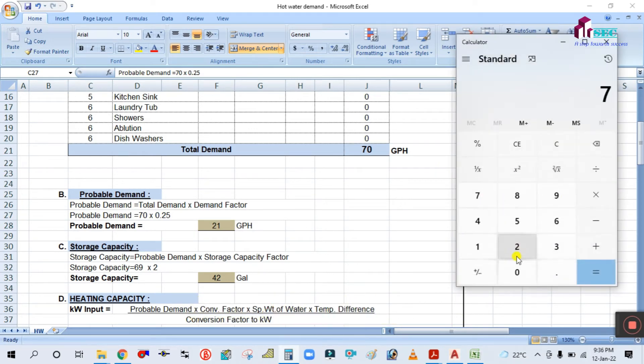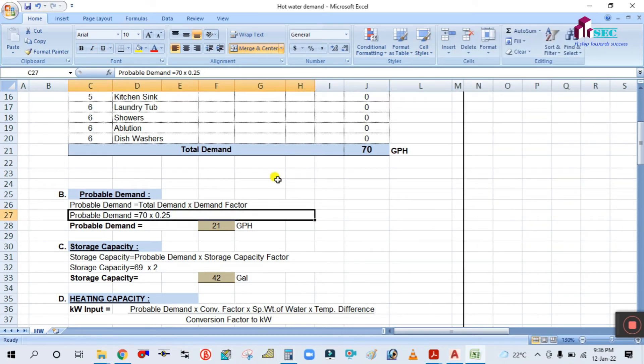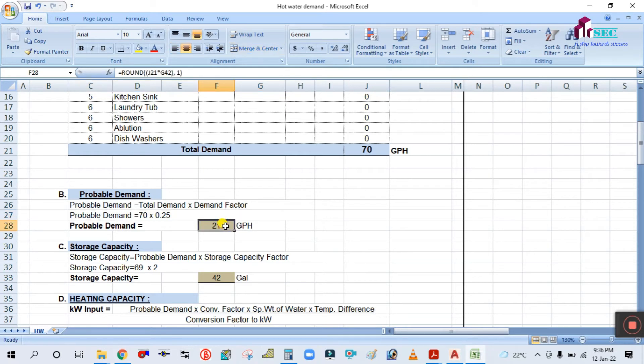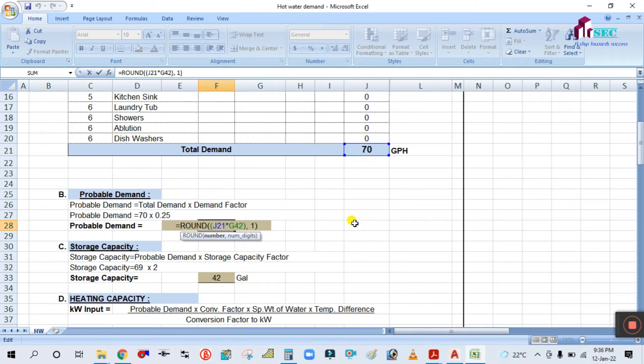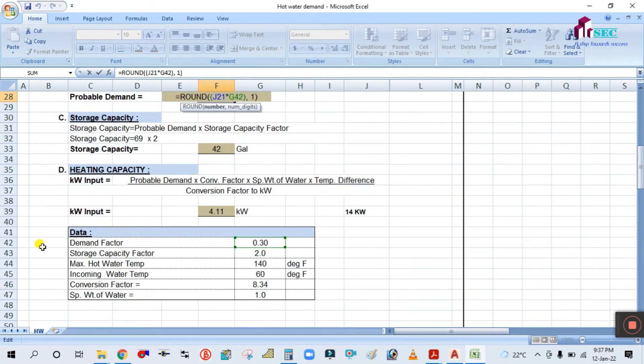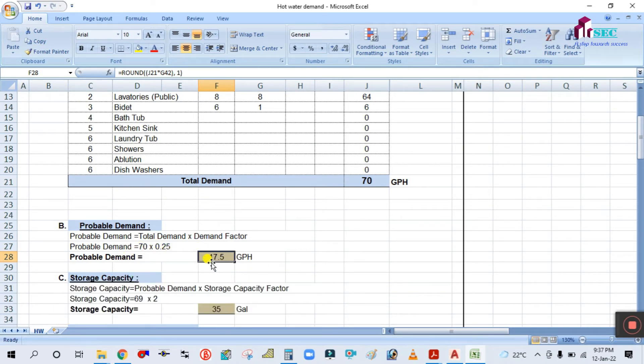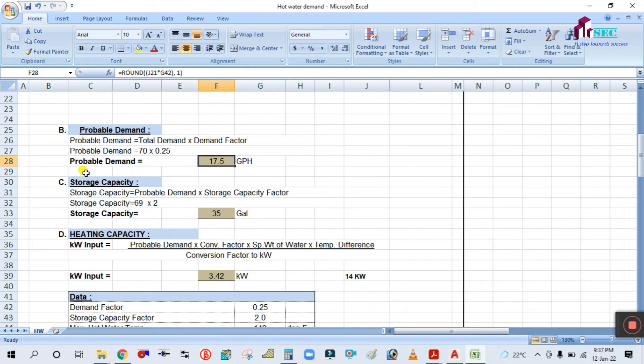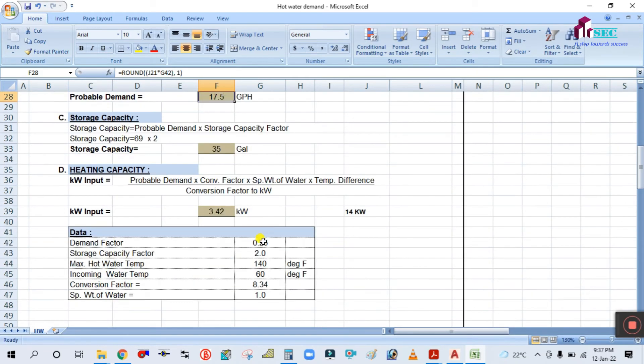Probable demand = 70 × 0.25 = 17.5 GPH. If you change the demand factor value — simply enter 0.25 — it will automatically update the probable demand. So probable demand is 17.5 GPH. It is total demand multiplied by demand factor, where demand factor is 0.25.